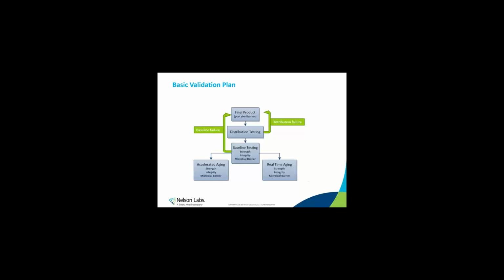Validation costs increase with longer final time points and with additional interim time points. After aging is completed, you repeat the same testing that was done on baseline for strength, integrity, and microbial barrier. And if you meet the acceptance criteria in your protocol, then you've proven that the sterile barrier system remains intact and effective through the expected expiration date.